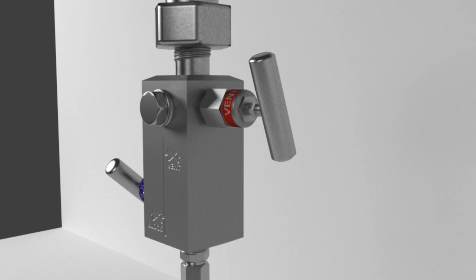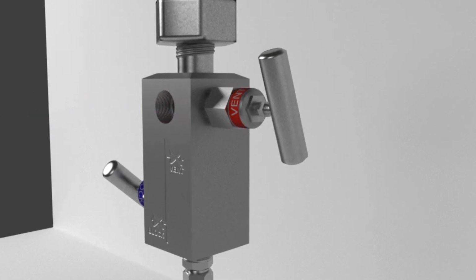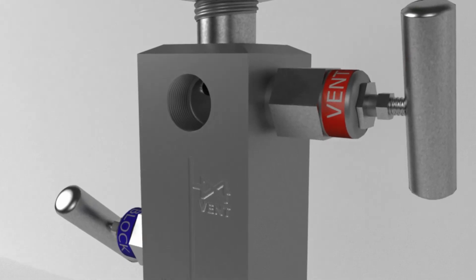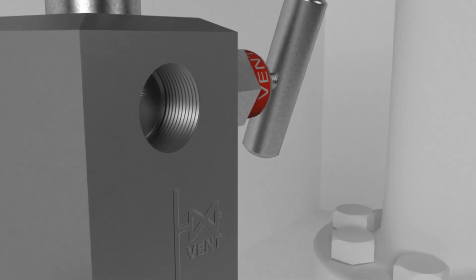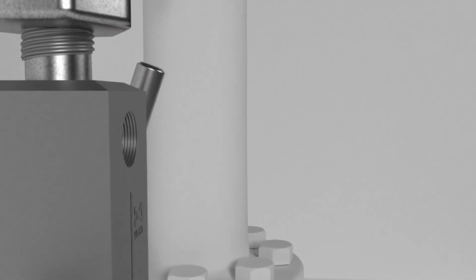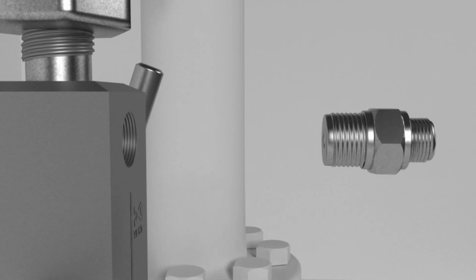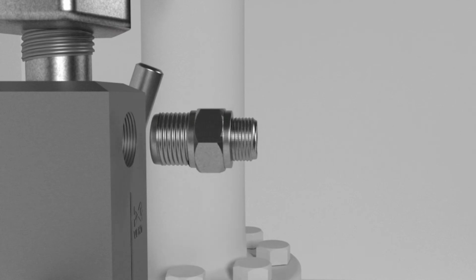If there is pressure in the line and you open the vent valve before removing the plug, the product in the line will spray out while removing it. This is especially hazardous while doing an ammonia or fuel line pressure calibration. After the product has vented or drained out, connect your tubing for your pressure calibration.